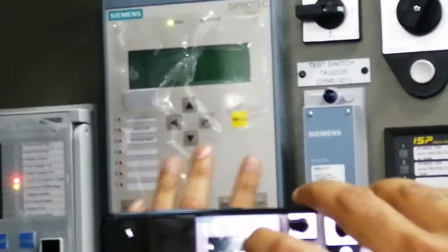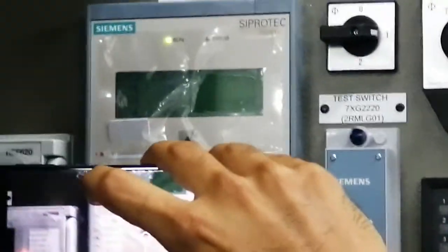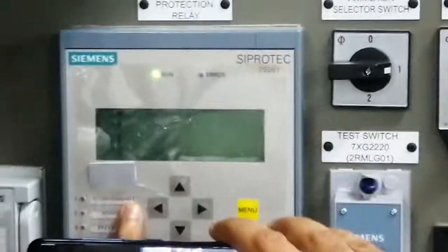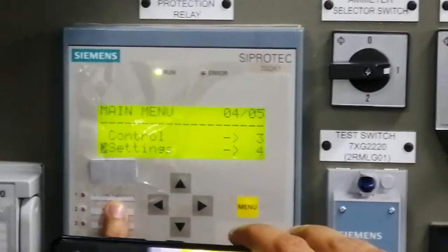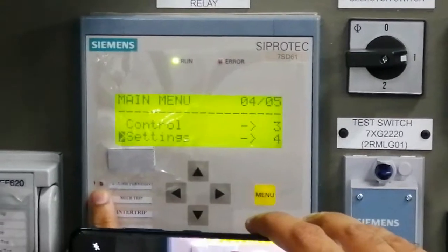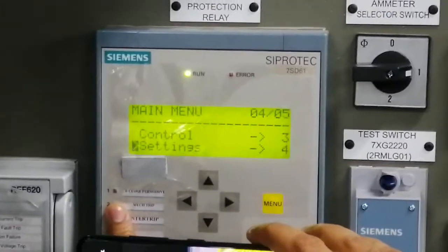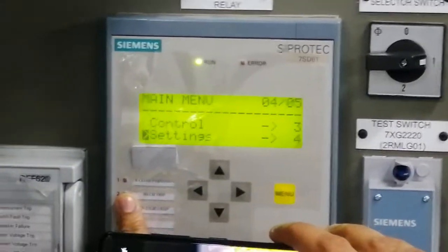So this is the 132 kV SIPROTEC relay. Right now we have configured this relay as 132 kV SIPROTEC, and we have also configured LED number 1 of this SIPROTEC relay as a CB close permissive. So this is the 132 kV CB close permissive. We don't have the permission right now because on the 11 kV side the earth switch is in test position. So let's put the earth switch in service position, and then we will check the signal again.